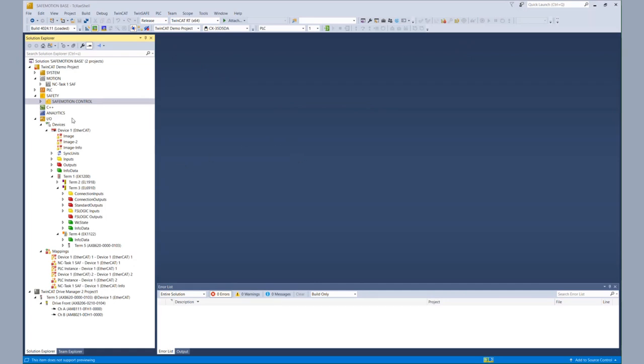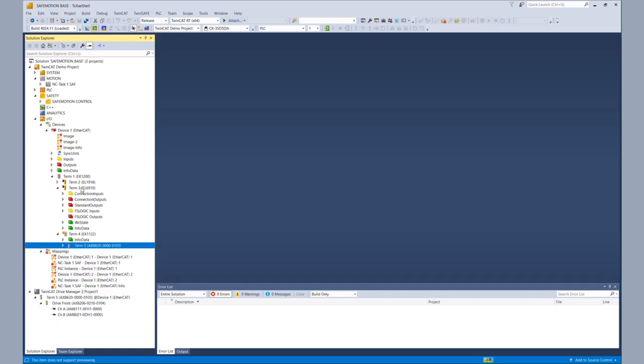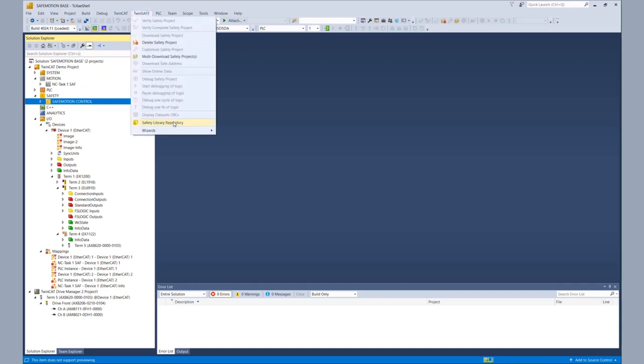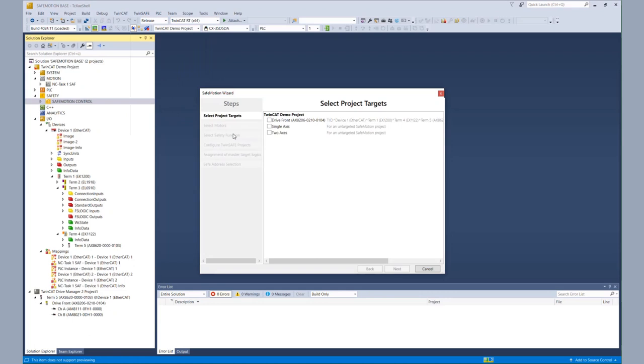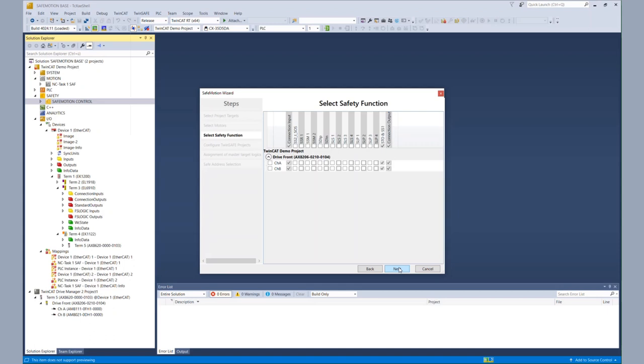Now it's time for our live demonstration. We have our TwinCAT 3 solution with the I/O configuration. We have our AX8000 in the X2XX version, our EL6910 and EL1918. The EL6910 is executing our safe motion control project. For the SLP, we start our SafeMotion Wizard. We choose our AX8000, configure the feedback — in our case it's a multi-turn feedback — and as safety functions for today's tutorial, we choose the SLP1 functionality for channel A. That's all we need today.